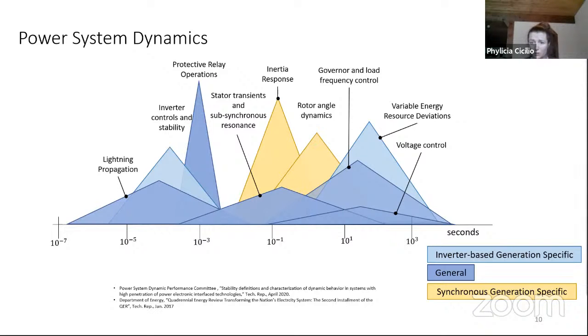You'll notice that inverter controls and stability dynamics occur much faster than the other dynamics, with the exclusion of lightning propagation. However, lightning propagation is a specific phenomenon that is not a very typical event simulated in system level studies. So you can see the inclusion of inverter-based generation is driving the need for faster timescale simulation of events to be able to control and maintain the stability of the system.